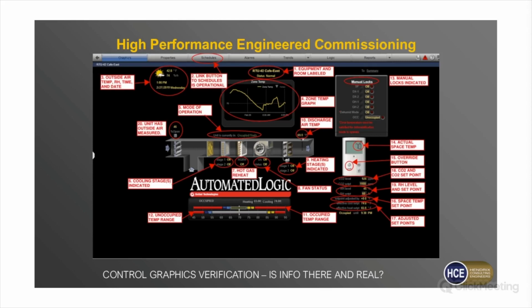Then as we move into the controls, there are so many things, and you're seeing that here. I think on this page, there's close to 20 items that need to be verified just on one unit. Verifying that the info here is real, that the points are landed where they're supposed to be landed, that your temperature reading in this, like number 14, is it really 70 degrees in the space, or is it 74?